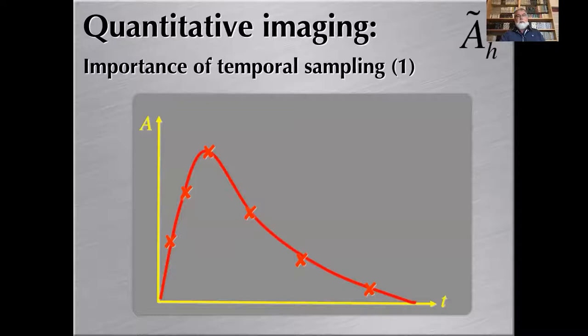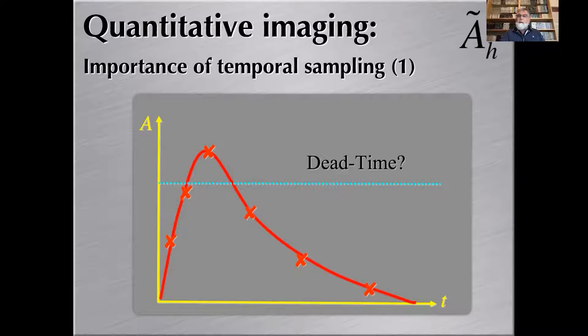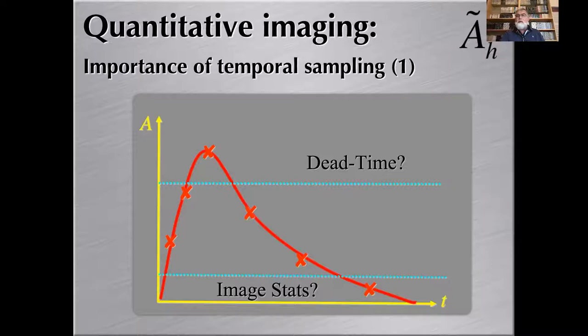We want to sample the time activity curve, and obviously the temporal sampling is going to be very important. You can see here the variation of activity as a function of time sampled by six time points. We have to pay attention to different aspects in the pharmacokinetics. Because we are in a context of therapy using quite high activities, dead time may occur especially at early time points. We have to identify the possibility of dead time and do the required corrections. On late images, we may suffer from the lack of statistics due to the decrease of activity.